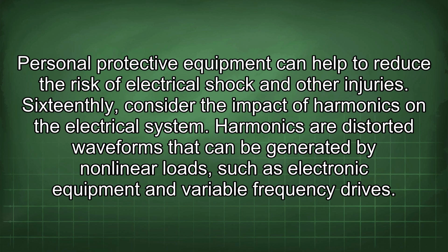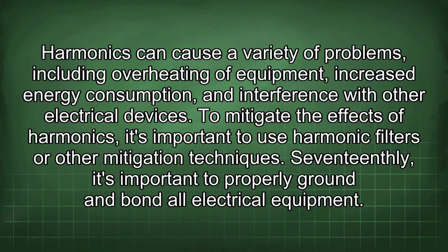16thly, consider the impact of harmonics on the electrical system. Harmonics are distorted waveforms that can be generated by nonlinear loads such as electronic equipment and variable frequency drives. Harmonics can cause a variety of problems, including overheating of equipment, increased energy consumption, and interference with other electrical devices. To mitigate the effects of harmonics, it's important to use harmonic filters or other mitigation techniques.